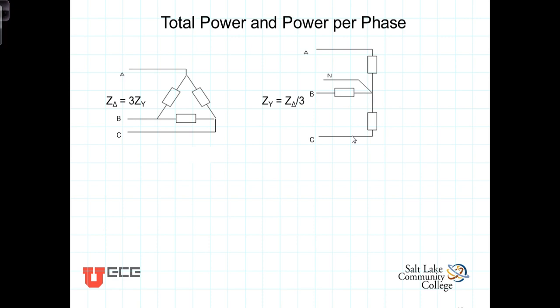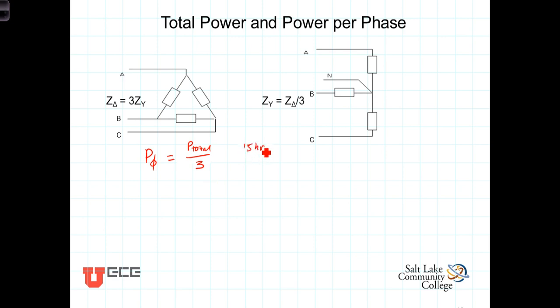Whether it's a delta connected load or a Y connected load, most of our calculations are done on a per phase basis. Therefore it's necessary to take that total power and come up with a per phase power. We're going to call the per phase power P sub φ (phi). That's the per phase power, equal to the total power divided by three. So for example, if we had a 15 horsepower motor, each phase would produce five horsepower — that 15 horsepower would be distributed across the three phases evenly.